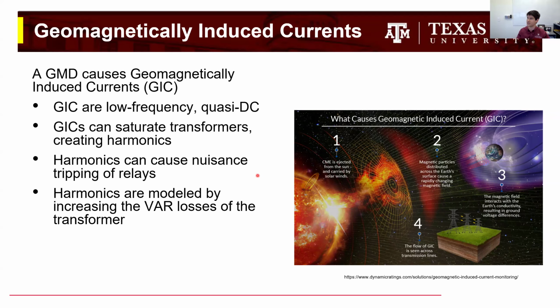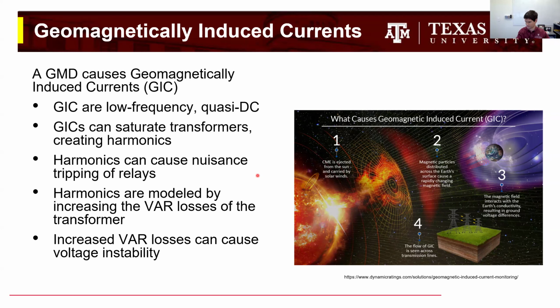The fundamental component of the voltage can start to drop because of the harmonics, and we model this as an increase in VAR losses on the transformer. So if you have a substantial increase in VAR consumption of the transformers, you can have voltage stability problems.